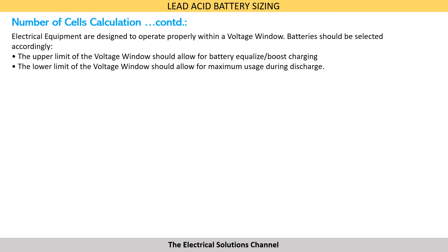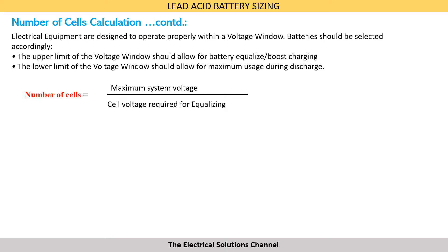Electrical equipment are designed to operate properly within a voltage window. Batteries should be selected accordingly. The upper limit of the voltage window should allow for battery equalizing or boost charging, whereas the lower limit of the voltage window should allow for maximum usage during discharge. Accordingly, the number of cells can be calculated as maximum system voltage divided by the cell voltage required for equalizing.